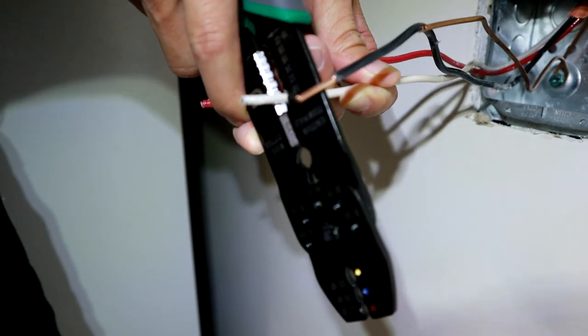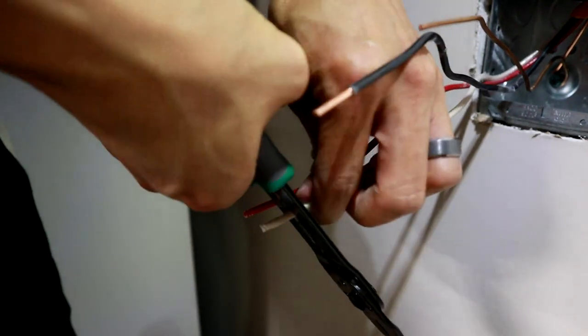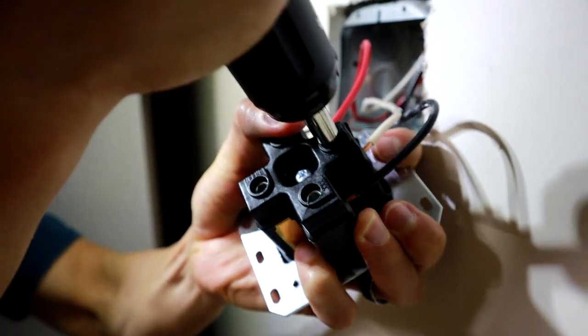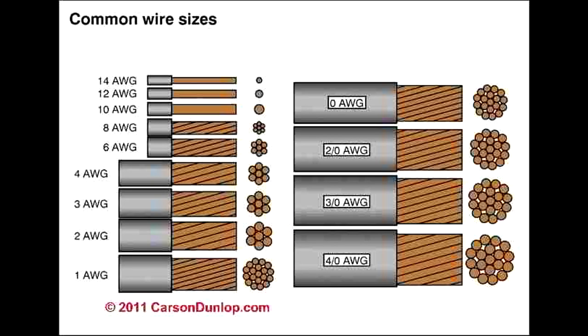There's also the install factor. For my NEMA 14-50, it cost me $500 to get the outlet installed and ready to go. Basically, you're going to pay at least that for a high-power wall charger because they have to do basically the same thing — wire up the breaker from your sub-panel or main panel and bring the wires to wherever you want the charger or outlet. On top of that, the high-power wall charger uses a 60-amp breaker whereas the NEMA 14-50 uses a 50-amp breaker. The higher the breaker, the thicker the gauge wiring you need, which means it might actually cost more to hardwire in a high-power wall charger to be compliant and safe, because thicker gauge wiring is really expensive.